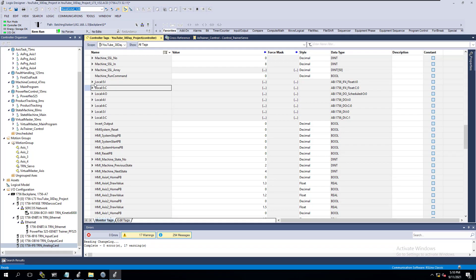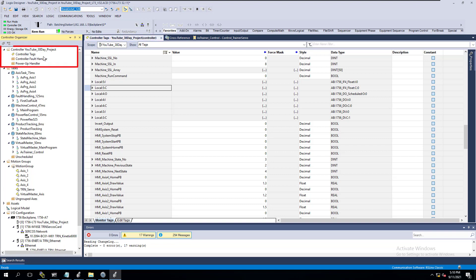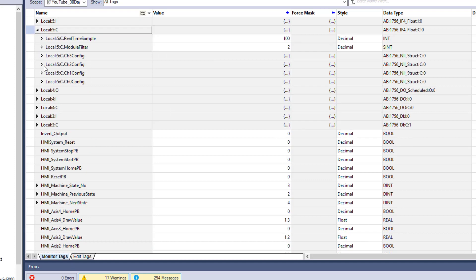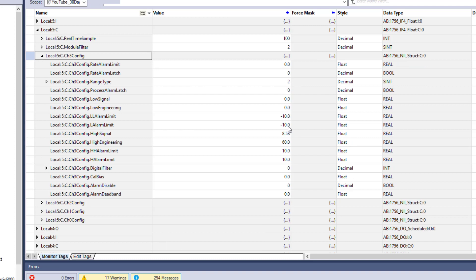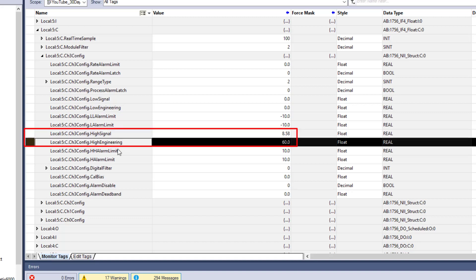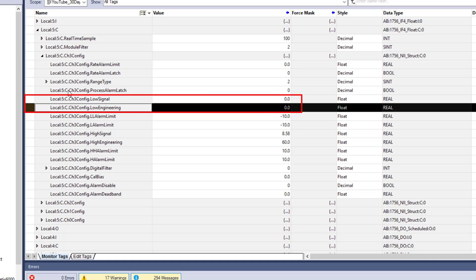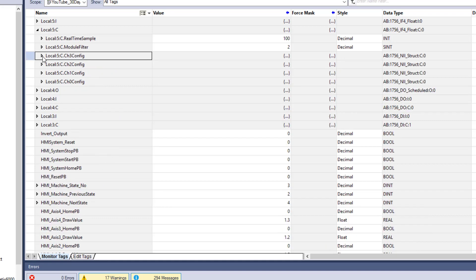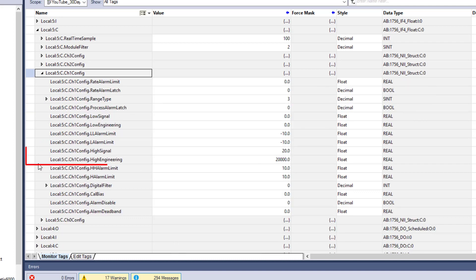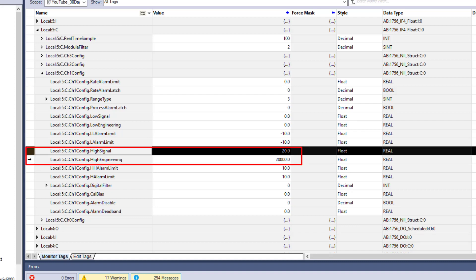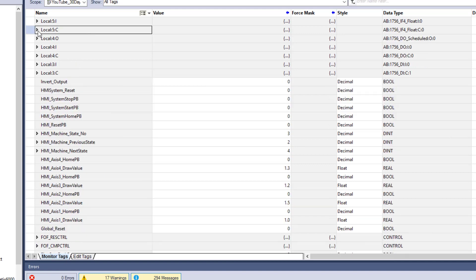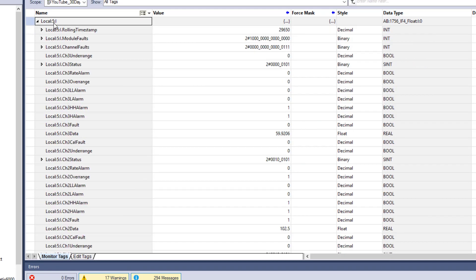If you want to see how the actual configuration and IO are laid out, come over here to your controller tags. This is going to be Local Card 5. First I'll have my inputs, and then I can look at my configuration for each channel — like Channel 3 configuration — where you can see all the settings I have configured: the high signal, high engineering units, low signal, and low engineering units. If I look at Channel 1, which is my 4-to-20, you can see the high engineering units at 20 milliamps equals 20,000.